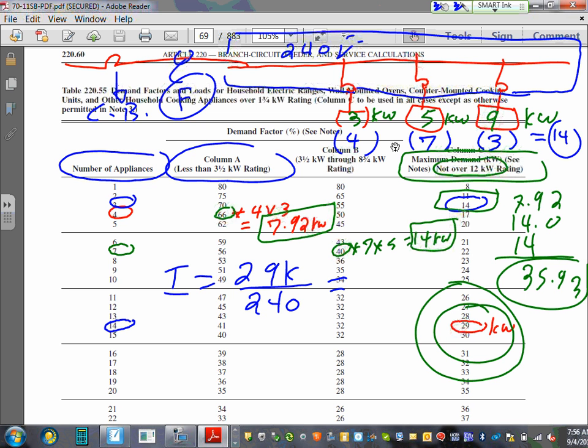29,000 divided by 240. 120.8 is good enough. 120. 121. 121 amp. Right? 121 amp. Okay, then now 120 amp. These are residential. Do me a favor. I would like you guys to go to the table that talks about residential and size this service.